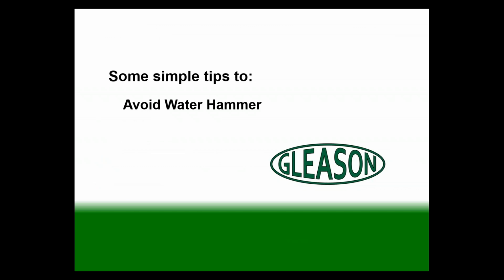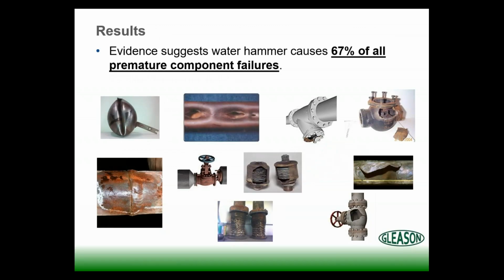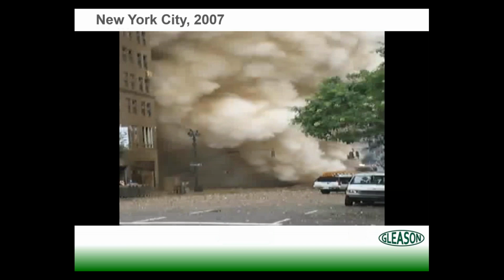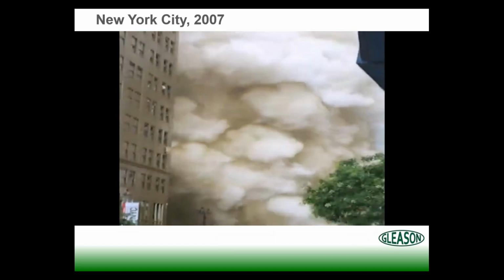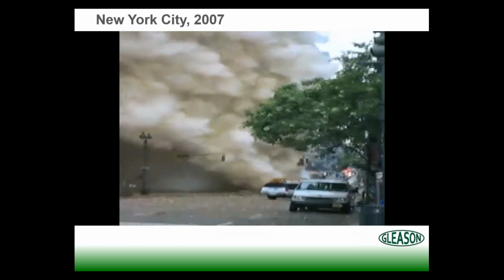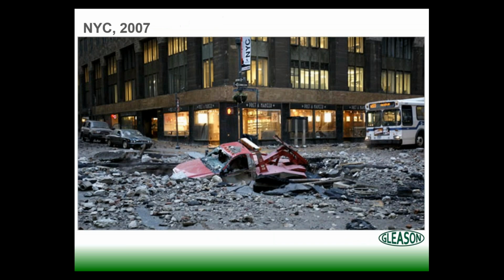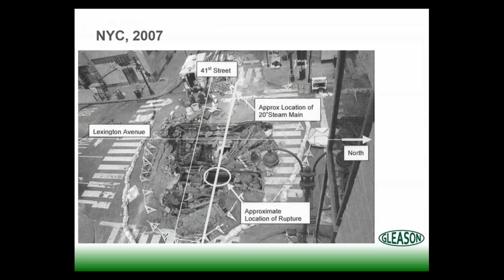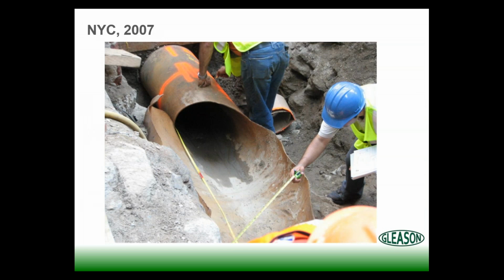So some simple tips to avoid water hammer. Evidence suggests that about 2/3 of all premature component failures in your steam or condensate system are due to water hammer. So this was a water hammer incident there, as I mentioned, in the summer of 2007. Here's the crater it left. Here's the piece of pipe itself. That was a water hammer event.